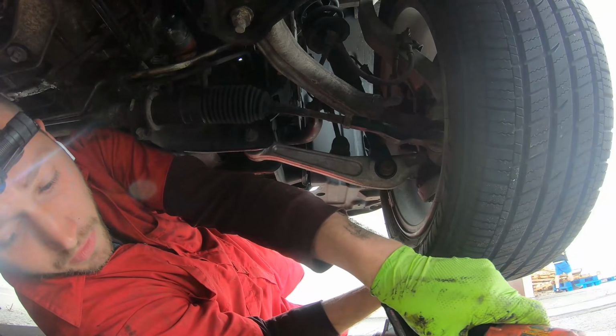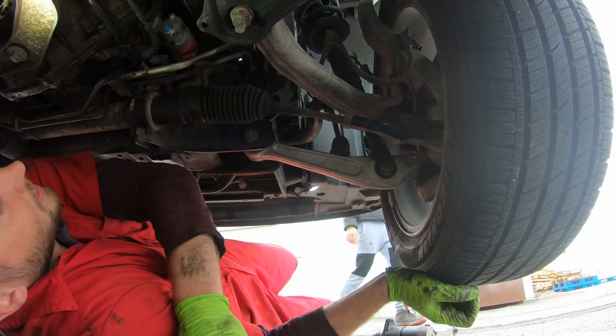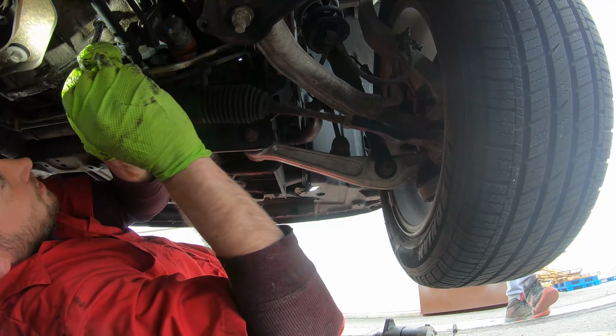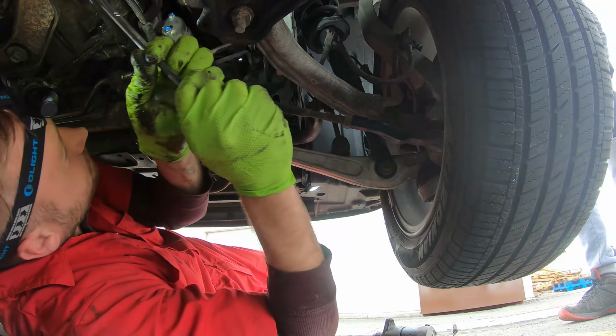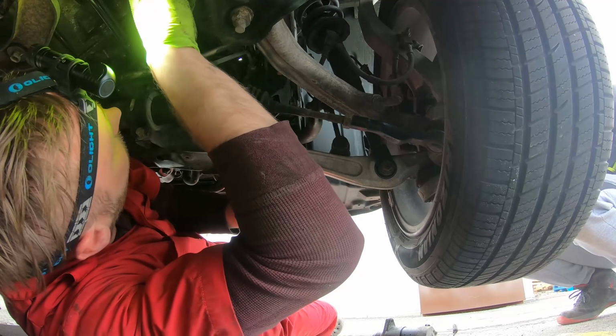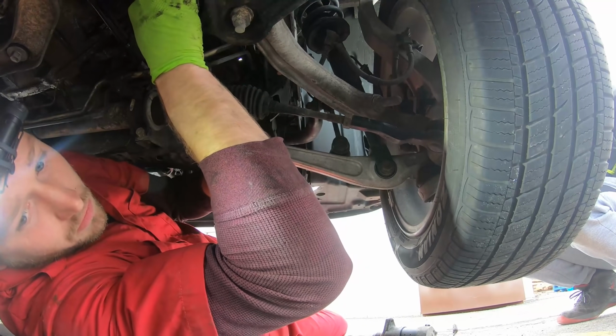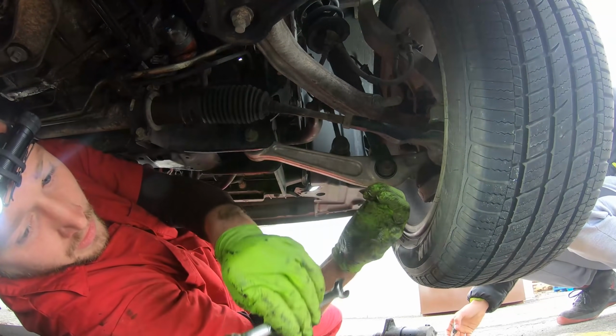Those two are tightened down. We'll finish them off with a wrench. You don't want to over tighten them, that's a mistake a lot of people will make. So just make sure they're torqued down. Usually like 18 foot-pounds will do it. This one, I think it's like 24, 26, so tight there.